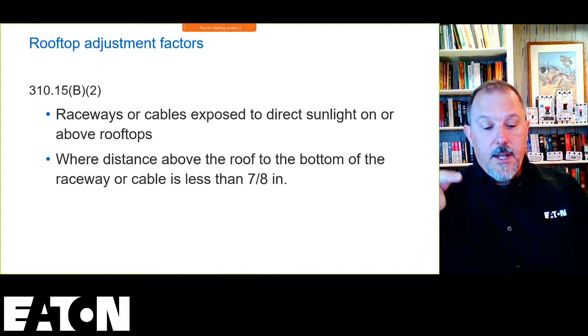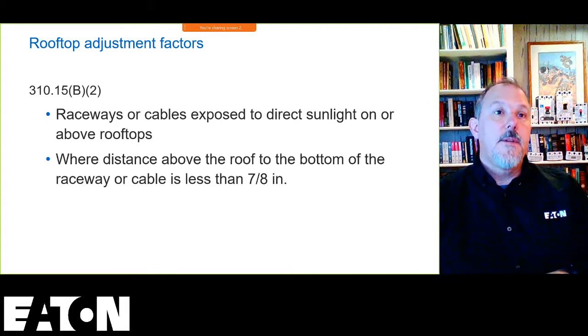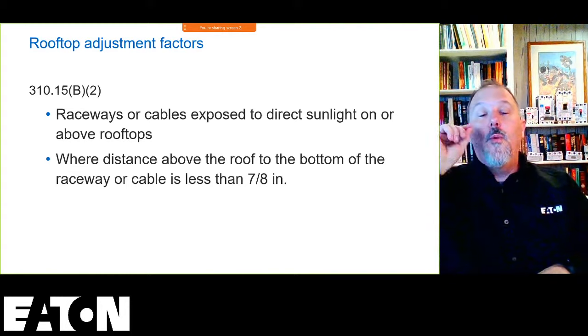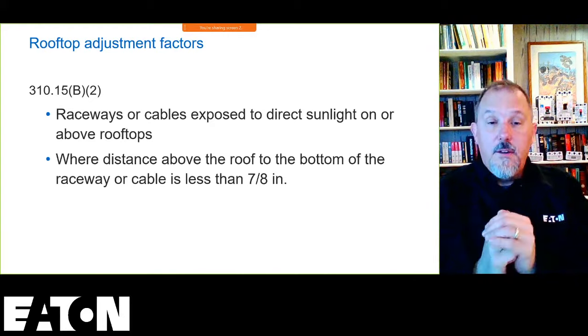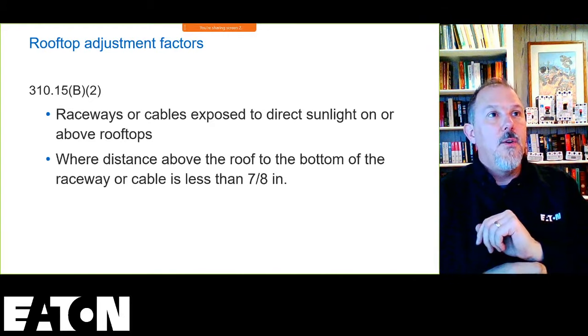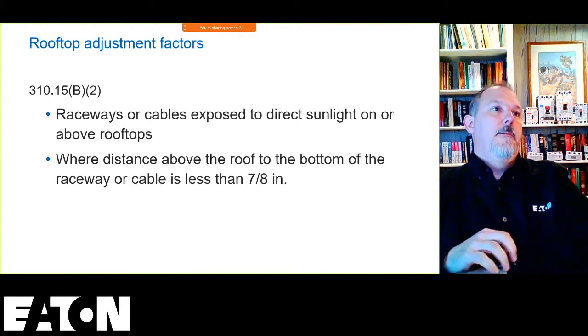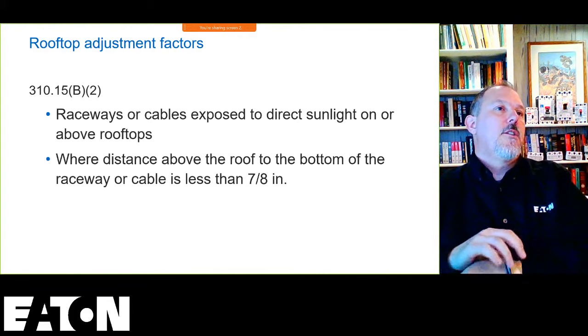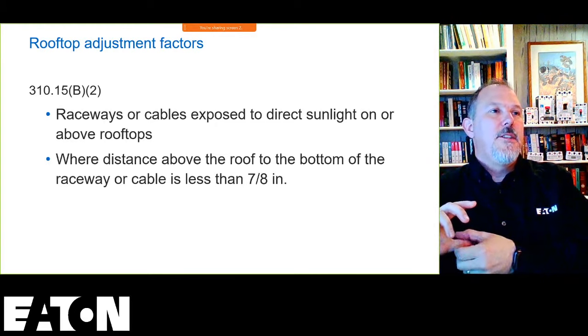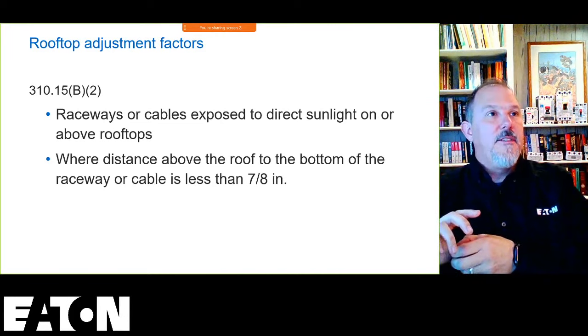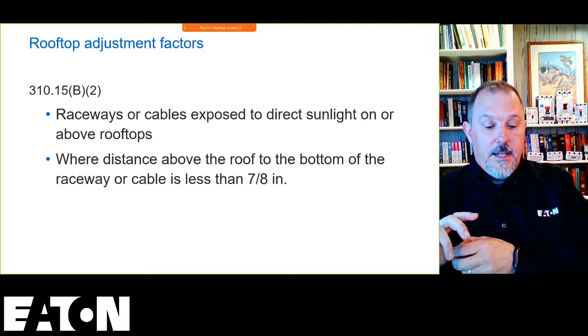All right, so take a look at 310.16. In a dry location, 75 in a wet location. Okay, good point. When I'm in a raceway, when I'm in conduit, is that a dry or wet location? I'll look for the chat. Most installations on a roof are exposed to sunlight. Yep, thank you, Ryan. Wet location, 300.9. And that's why we're using that 75 degree C for THHN and THWN, primarily because it is a wet location.